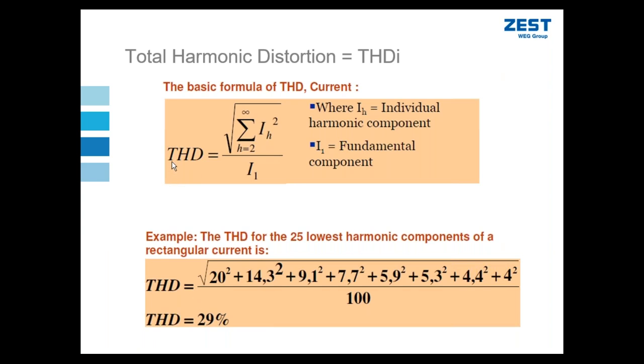All right, so looking at the formula for THD, what we do is we find the root mean square of each individual harmonic, starting from the second order harmonic. In other words, we ignore the fundamental and we square each of those harmonic contributors and we add them together, and then we divide it by the amplitude of the fundamental, and that gives us THD as a percentage, and that allows us to analyze and compare and restrict by standard, etc.